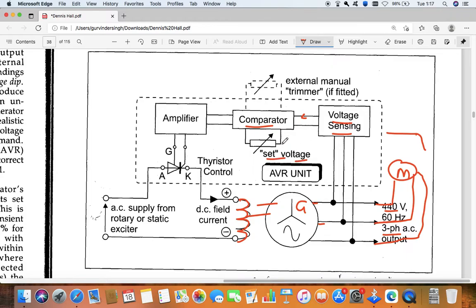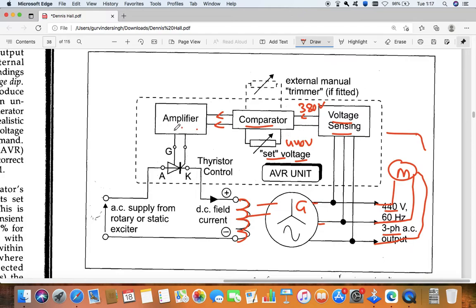The comparator will compare it with the set value. The set value is compared with whatever voltage we are getting. For example, here we are getting 380 volt and we have a set value of 440. So from here we will get an error, and that error signal is sent to the amplifier, where the amplifier will amplify the signal. After amplifying the signal, it will send the signal to the thyristor.